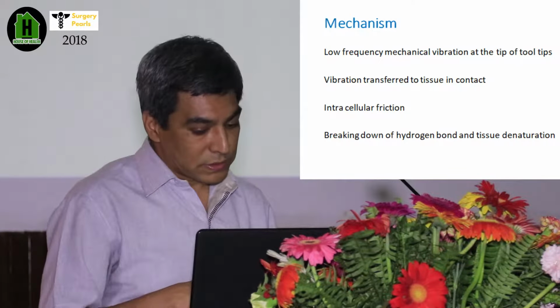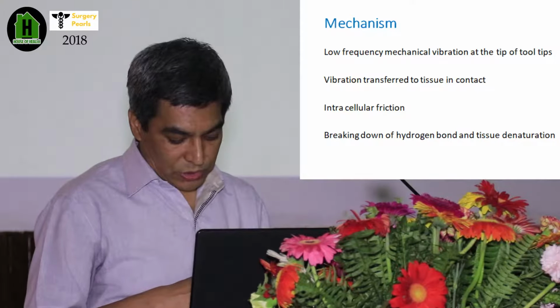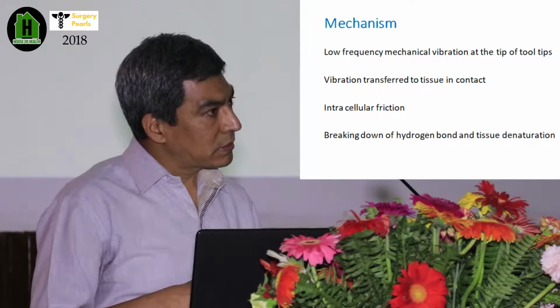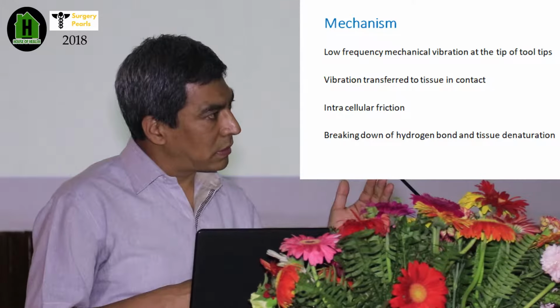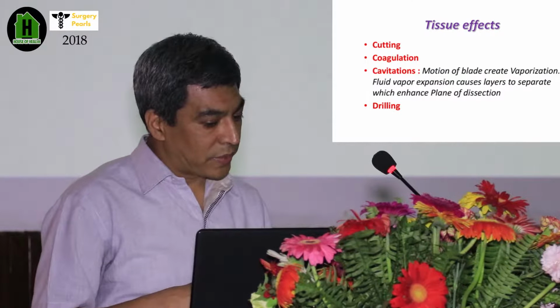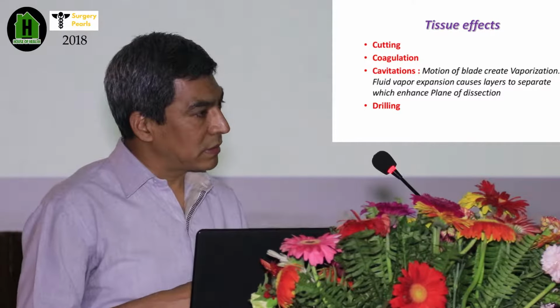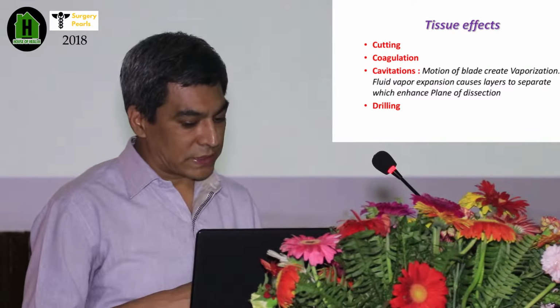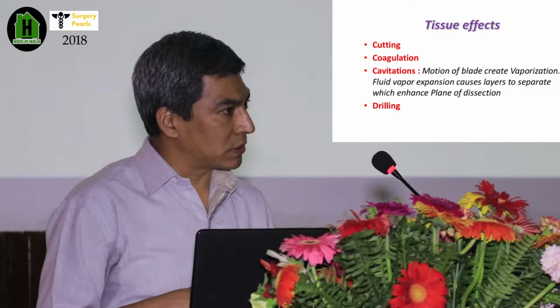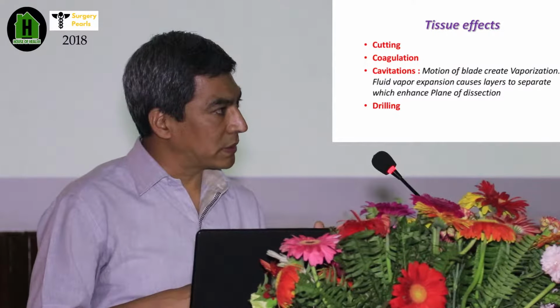Now the ultrasonic system uses a frequency of 20 kHz, which is higher than audible. It gives a similar effect to electrosurgical units, such as cutting, coagulation and drilling, but cavitation is peculiar to ultrasonic devices. It will cause vibration of the tissues, and the tissue will be vaporized. So it's called cavitation.